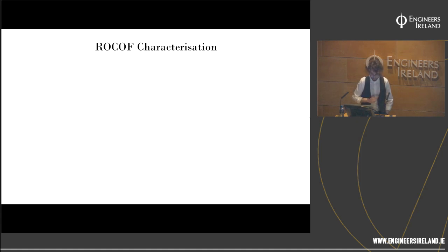There are two parts to the RoCoF equation: the size of the contingency, and the inertia that you have online. And what can happen sometimes is at higher wind penetrations, your largest in-feed is not as big as it was at lower wind penetrations. So you need to be careful. To guard against rate of change of frequency, RoCoF, you need to characterize it.